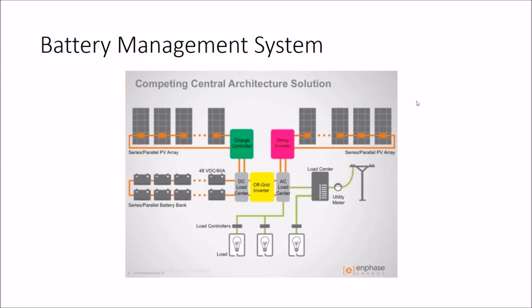Let's see. Battery systems are more functional. As far as AC coupling and DC coupling go, you can actually mix and match it all together. The main rule is you want to have one battery inverter, or at the very least one battery inverter manufacturer. So you can double stack and triple stack and quadruple stack battery inverters, but you want the battery inverters to all be the same.